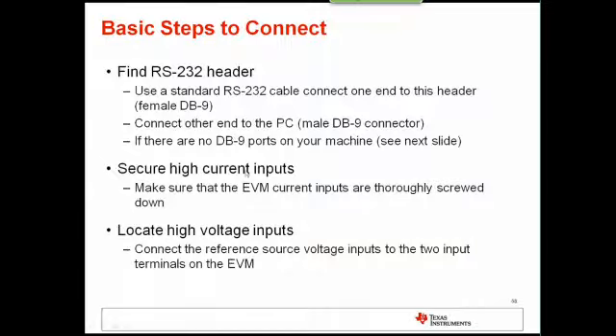Then secure any high current inputs - you'll have to crank down on those screws to make sure they're really secure if you're going to be pushing 100 amps through this thing. Same with the high voltage inputs; make sure those are securely connected if you're going to run this onto a test setup.